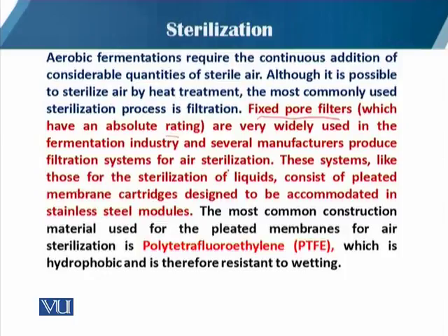These systems, like those for the sterilization of liquid, consist of pleated membrane cartridges designed to be accommodated in stainless steel modules. The most common construction material used for the pleated membrane for air sterilization is polytetrafluoroethylene, commonly known as PTFE. Polytetrafluoroethylene is hydrophobic and is therefore resistant to wetting. So the filter will not be wetted.